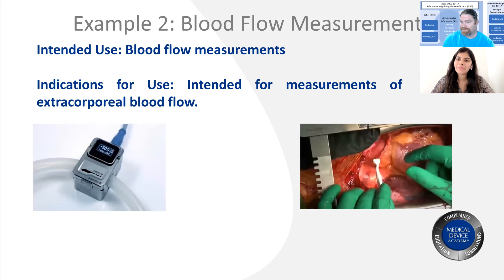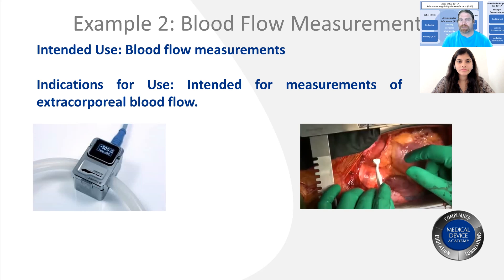Here are a couple more samples. Similar to what we showed on the first slide, blood flow measurements — on the left-hand side, the example of an extracorporeal measurement. If this were a hemodialysis system, you'd be measuring blood flow through tubing, so it's non-invasive and non-sterile, but still measuring blood flow. Whereas the example on the right is someone measuring blood flow invasively during heart surgery on a blood vessel rather than through tubing, and it's sterile. Very different indication for use. The intended use is blood flow, but the indication for use is much more specific.